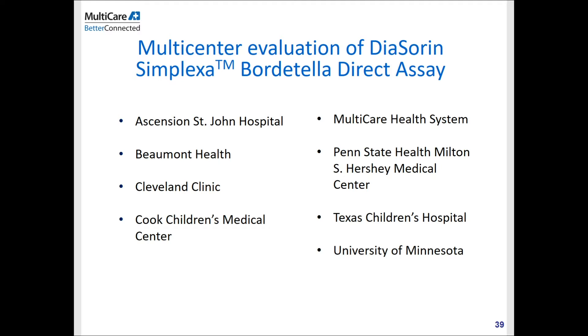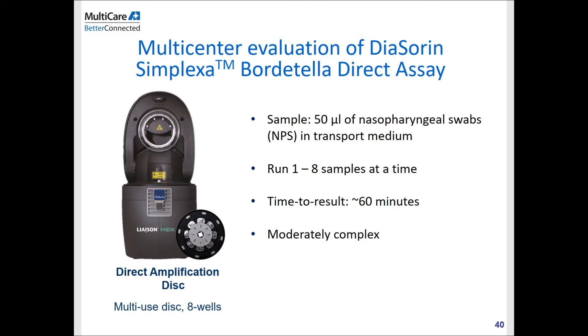The multi-center evaluation of the Diasorin Bordetella direct assay was conducted at eight hospitals: St. John Hospital, Beaumont Health, Cleveland Clinic, Cook Children's, MultiCare Health System, Hershey Medical Center, Texas Children's, and the University of Minnesota. The assay itself is very simple — a sample-to-result type assay requiring just 50 microliters of NPS in transport medium. You can run up to eight samples at a time with a run time of about 60 minutes. In our lab, we have multiple instruments that can run simultaneously, and we can run this assay around the clock including night shifts.